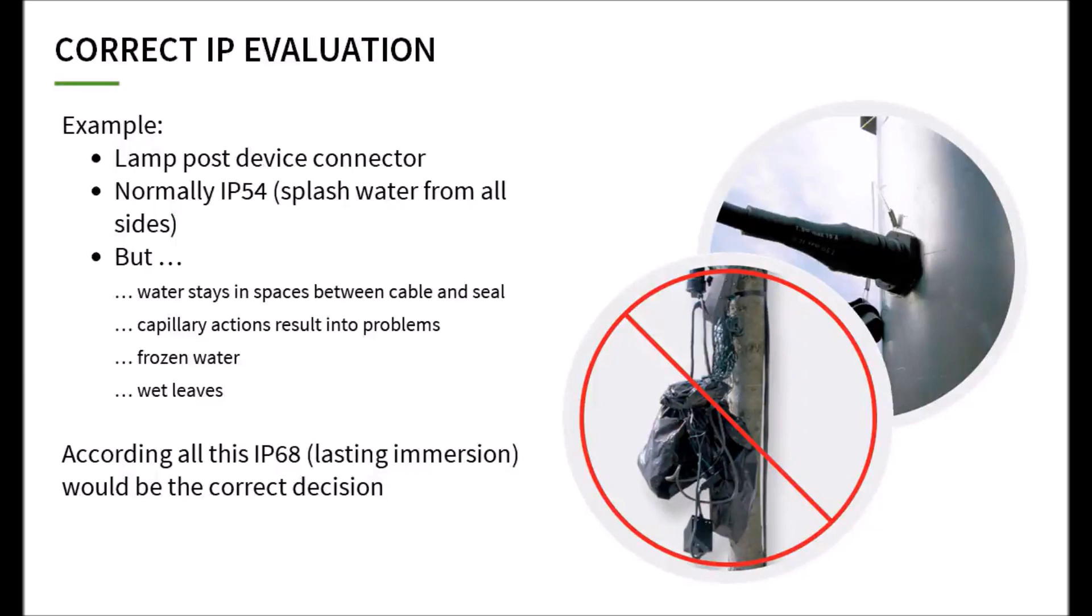It is always important to correctly assess the required IP protection class. Let us assume that a connector is to be inserted into a luminaire in the open air for power supply. By definition, the choice is IP54 protection. This means splashing water from all sides. However, a closer look at the sealing area reveals that it is sometimes completely covered with water for weeks.